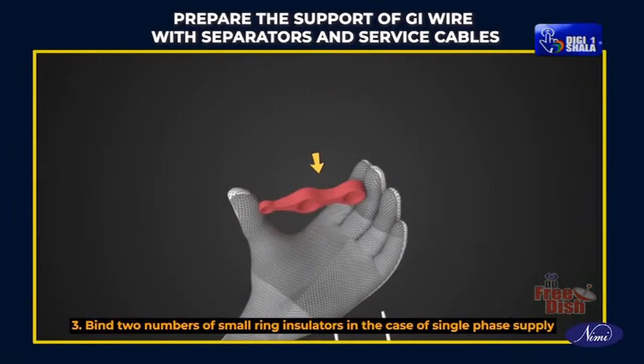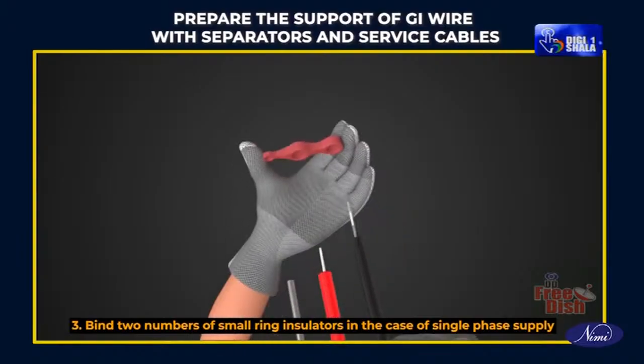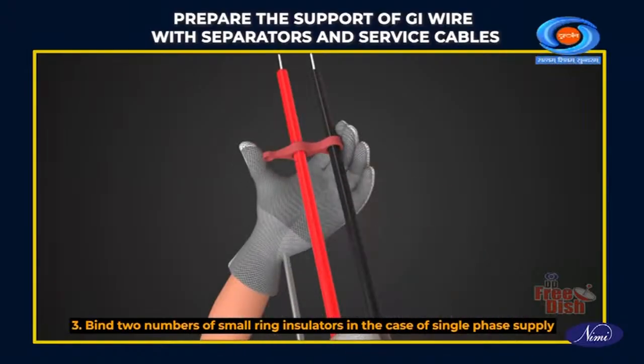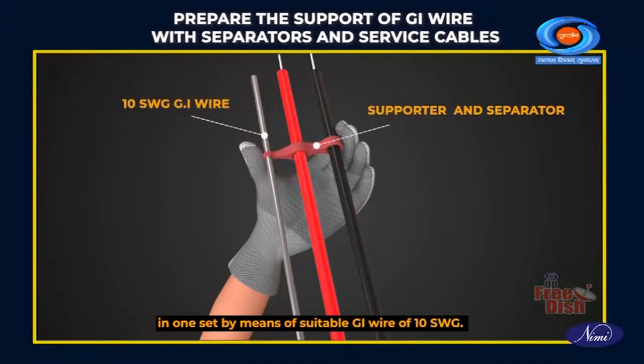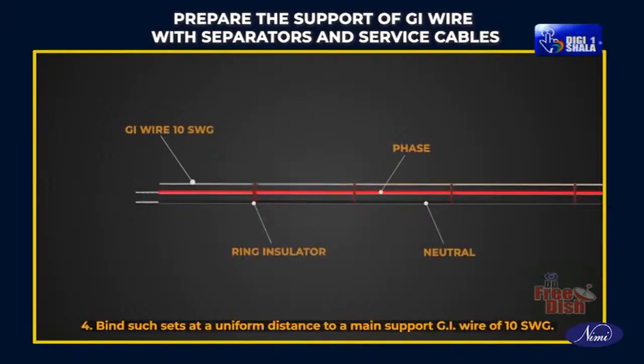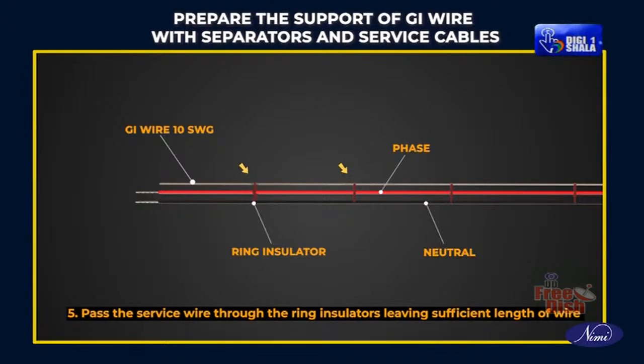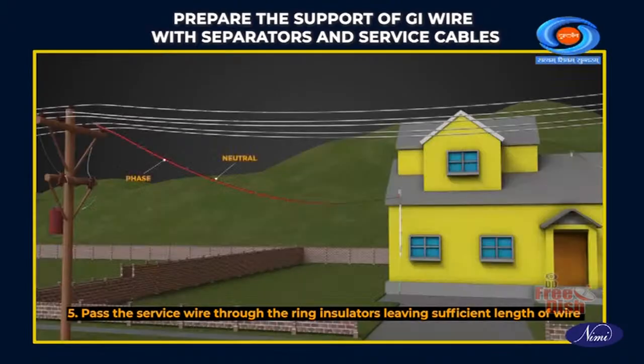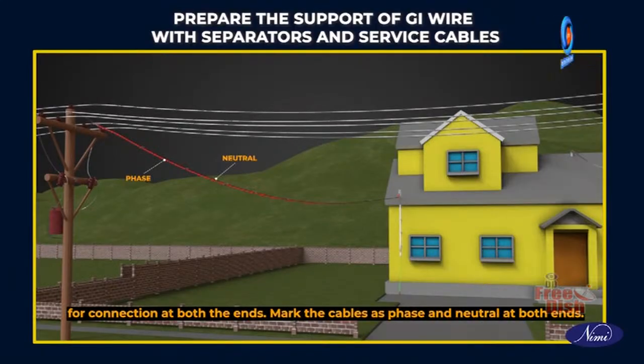Bind two numbers of small ring insulators in the case of single phase supply in one set by means of a suitable GI wire of 10 SWG. Bind such sets at a uniform distance to a main support GI wire of 10 SWG. Pass the service wire through the ring insulators, leaving a sufficient length of wire for connection at both the ends. Mark the cables as phase and neutral at both ends.